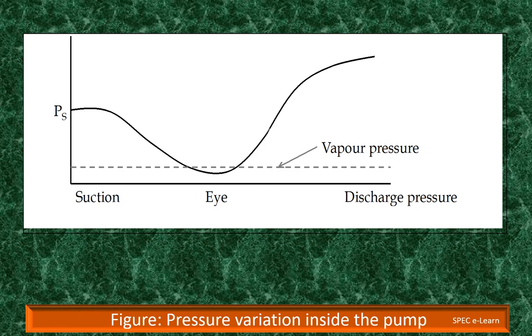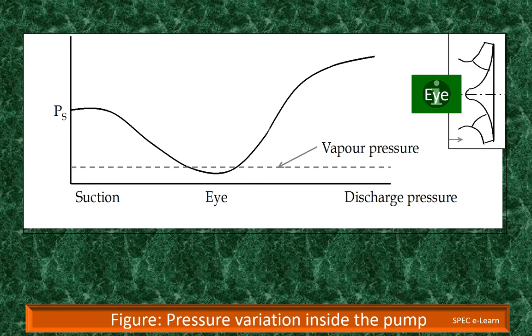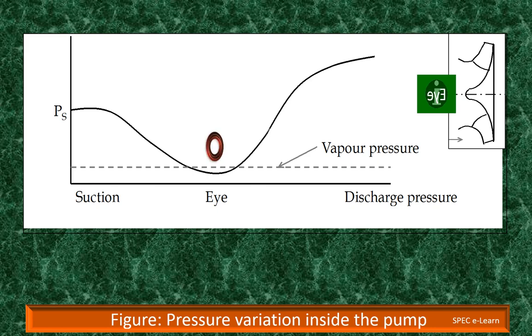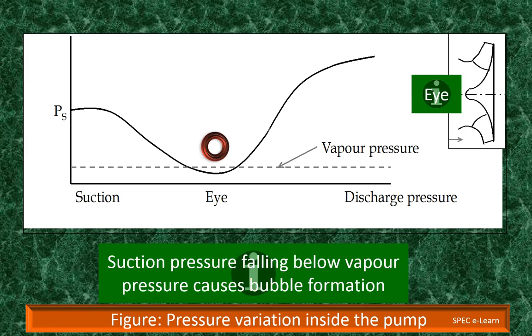This figure illustrates how pressure varies from the suction line to the eye of the impeller. As the liquid passes from suction to the impeller eye, velocity increases and pressure decreases. There are also pressure losses due to shock and turbulence as liquid strikes the impeller, and the centrifugal force of the impeller vanes further increases velocity while decreasing pressure. All these pressure losses contribute to a drop in system pressure at the impeller eye, and bubble formation is possible if the net suction head is not sufficient.